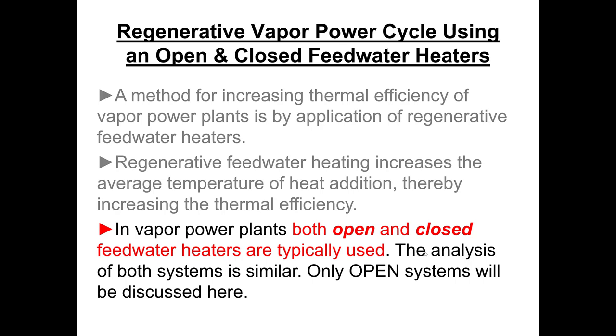In the open feed water system, both streams — the hot and the cold — are free to mix in direct contact, so it's basically a mixing chamber. In order for that to happen, the pressure of both streams must be the same. Since we're extracting steam from an intermediate pressure point within the turbine, we need to pump the condensate out of the condenser to that intermediate pressure, and then use a second pump to pump the condensate back to the steam generator.